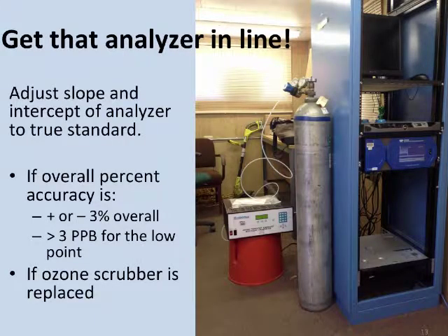So, yes, sure. Struggled with this, I guess, quite a while. Okay, so the as-is, I'm not pushing any buttons. I'm not doing this precision check. Would you call it that? A precision check would be a specific point. If I did a 4-point precision check, is that the same as your as-is calibration? Not quite.